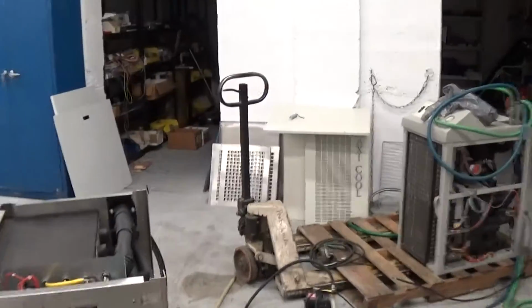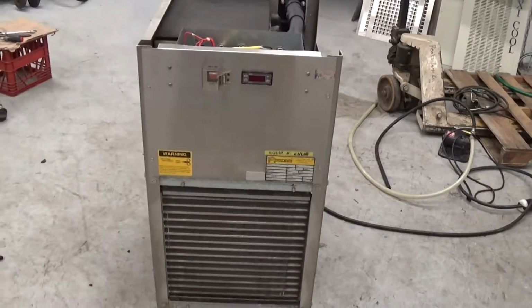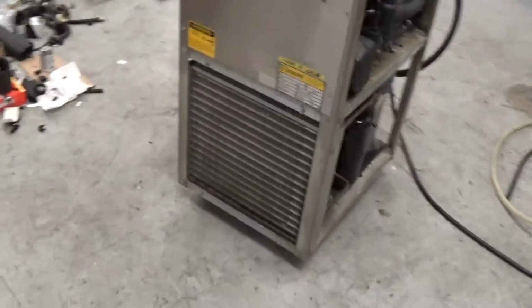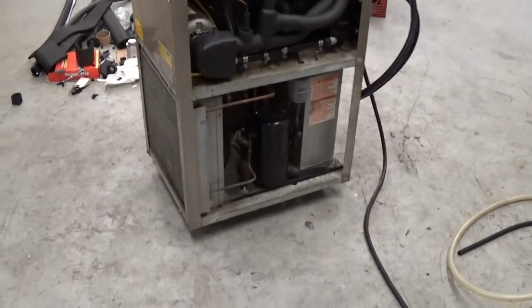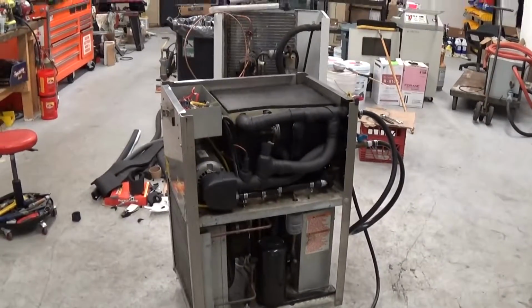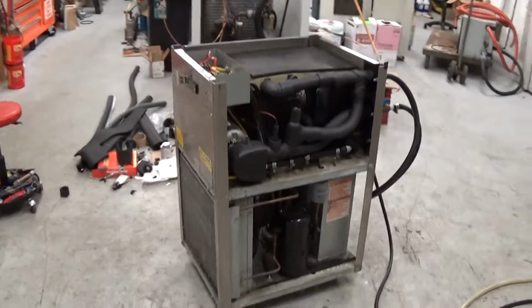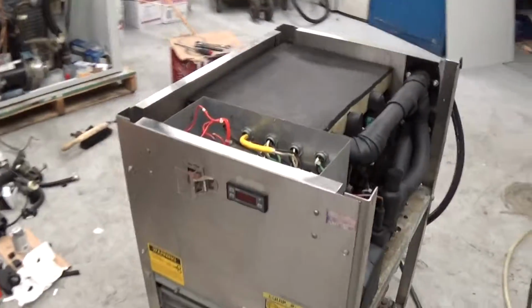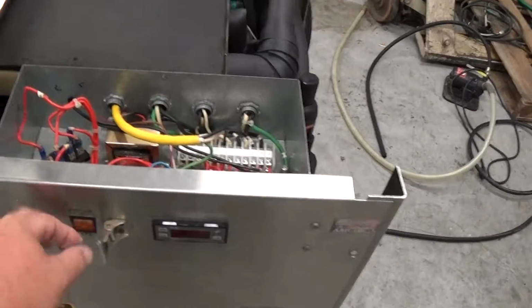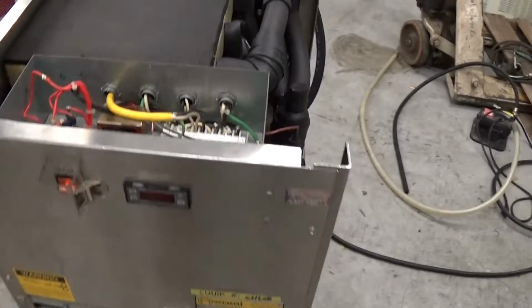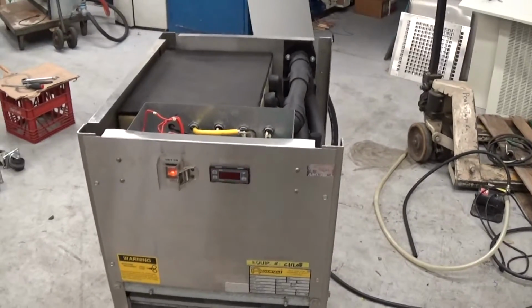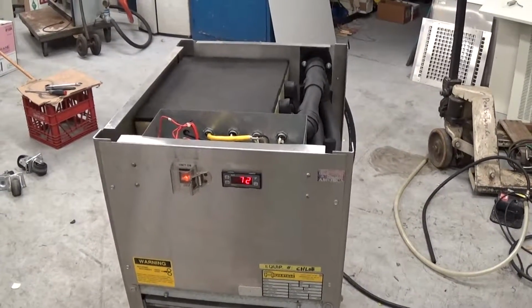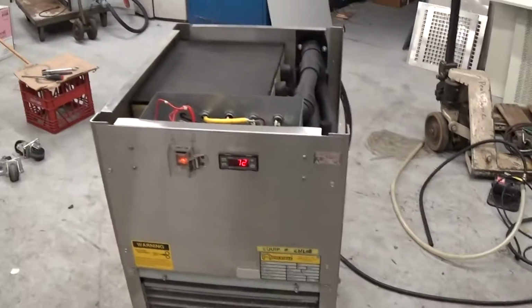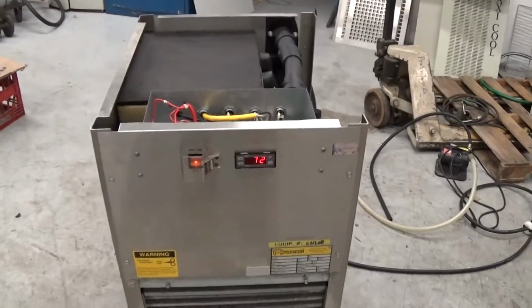We have the covers off. We'll leave the covers off. We're going to give it a quick cleaning before we crate it up. But usually, units like this, this particular unit does not need the covers on for appropriate airflow. Some chillers do. So we're going to simply power the unit up here. Just really basic 208 or 230 single phase power right into the chiller.